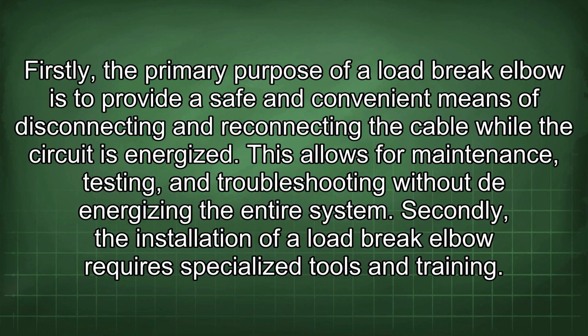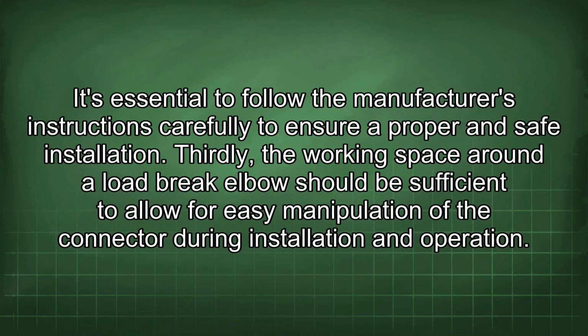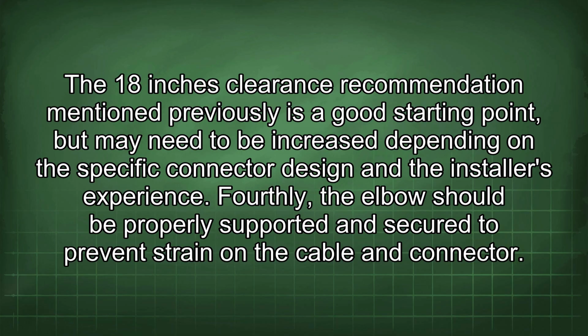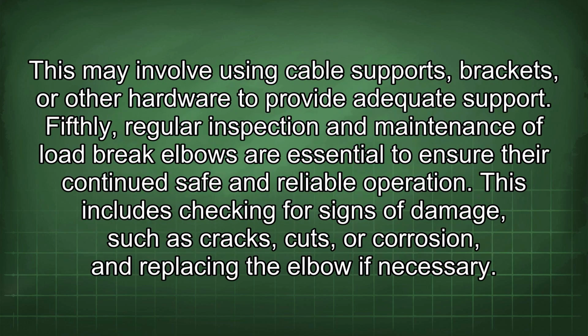Secondly, the installation of a load break elbow requires specialized tools and training. It's essential to follow the manufacturer's instructions carefully to ensure a proper and safe installation. Thirdly, the working space around a load break elbow should be sufficient to allow for easy manipulation of the connector during installation and operation. The 18 inches clearance recommendation mentioned previously is a good starting point, but may need to be increased depending on the specific connector design and the installer's experience. Fourthly, the elbow should be properly supported and secured to prevent strain on the cable and connector. This may involve using cable supports, brackets, or other hardware to provide adequate support. Fifthly, regular inspection and maintenance of load break elbows are essential to ensure their continued safe and reliable operation. This includes checking for signs of damage, such as cracks, cuts, or corrosion, and replacing the elbow if necessary.